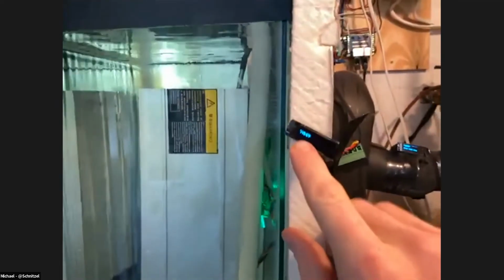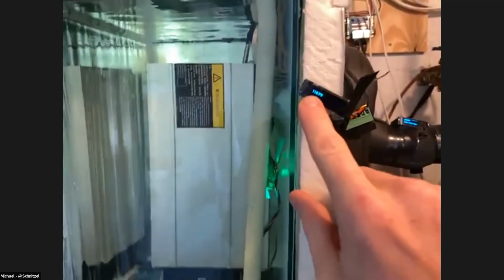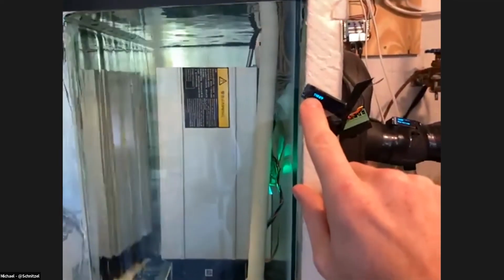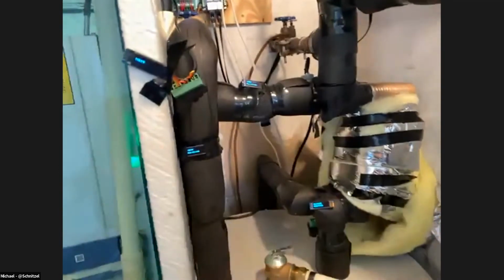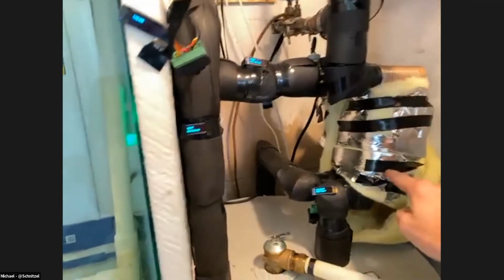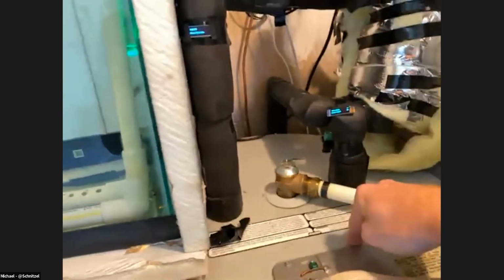So I turned off the water. You see the flow is now at 0. We see the bit cool in the meantime drops to 118 Fahrenheit. If you remember, it was like 140 before. It actually dropped quite considerably because the bit cool was still circulating, and cold water came through here into the system.